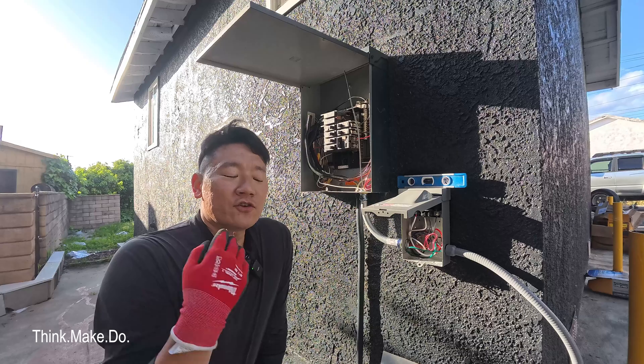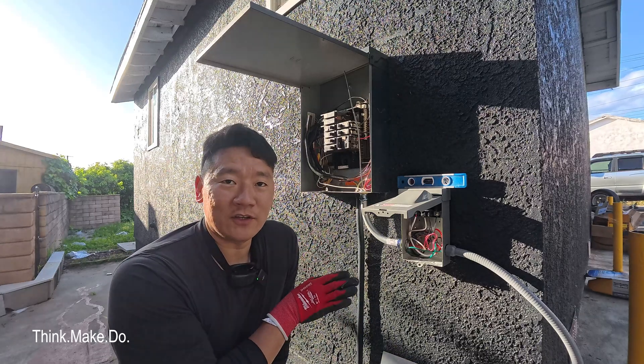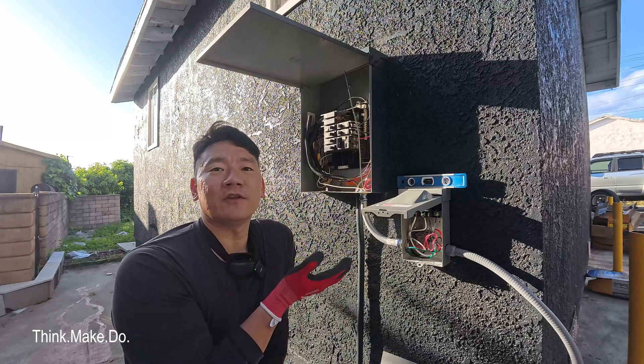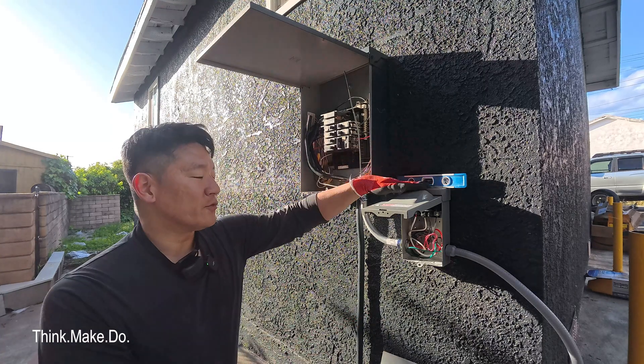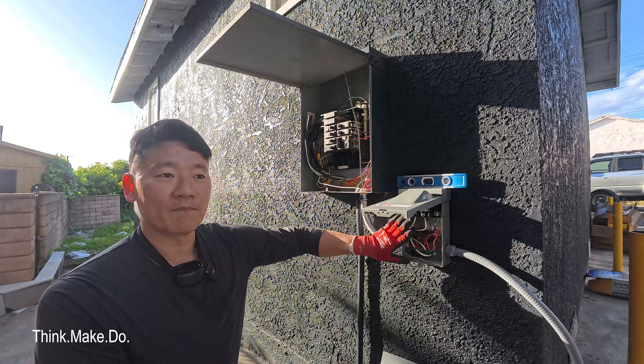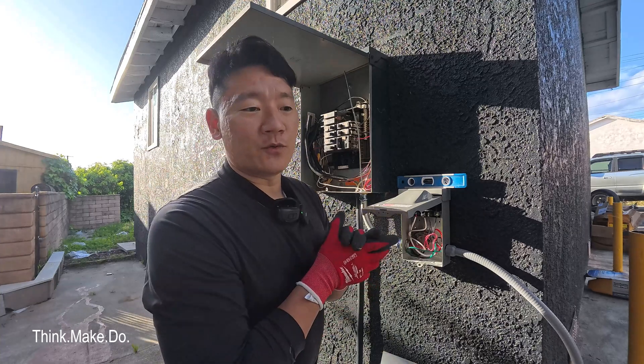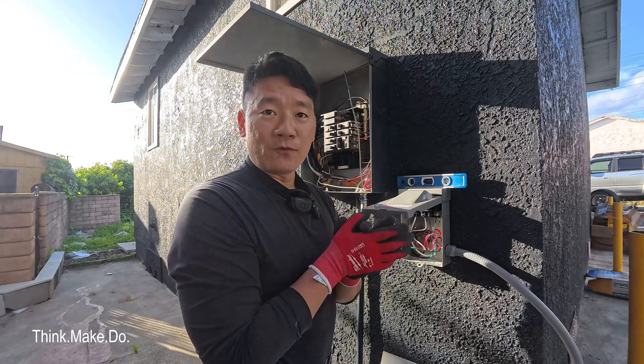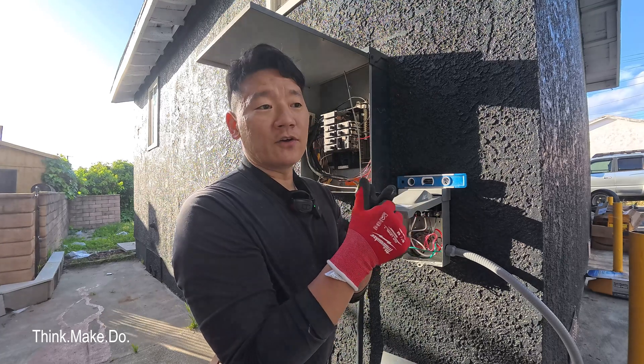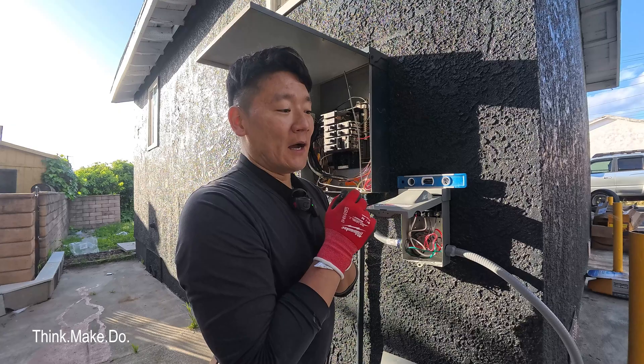Let's go over a few things here. This studio unit is going to be using a 120-volt AC system, not a 240-volt, but I bought all the same supplies because they're somewhat compatible. This breaker box is typically a 240-volt on/off breaker, however it is compatible with 120. The main difference between 120 and 240 is that the 240-volt has a red and a black for power and a white for common, and that's it.